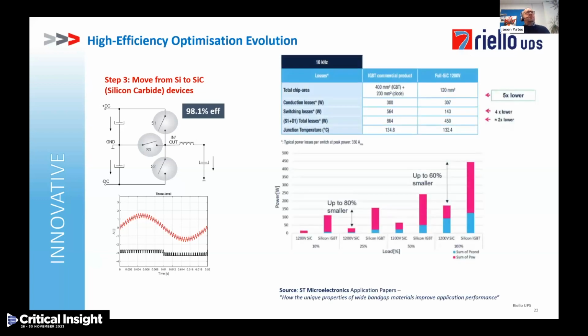If we look at these tables here and the graph, the table at the top is showing a comparison between a traditional IGBT and a silicon carbide device. As you can see, the total chip area of the silicon carbide device is around a fifth of the size of a traditional IGBT, so it makes our designs much smaller. The conduction losses are slightly higher for the silicon carbide device. In fact, they're roughly about the same, but again, slightly higher. But our switching losses are where we make our gains. As you can see, the switching losses through a silicon carbide device are around a quarter of that of a traditional IGBT. So in total, overall, we are producing around 50% less heat than a traditional IGBT.